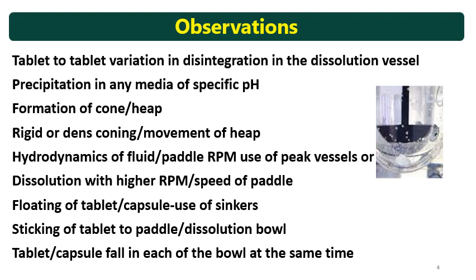Observe floating of the tablet or capsules — if they are floating, use sinkers. Also observe the sticking of the tablet to the paddle or dissolution bowl. If the tablet lands onto the bowl surface and is not going to the center, dissolution variation will occur. A tablet sticking to the side will dissolve faster because the hydrodynamics are greater there compared to a tablet landed at the center point. Also note if the tablet or capsule does not fall into the bowl properly, as that may cause variation in results.